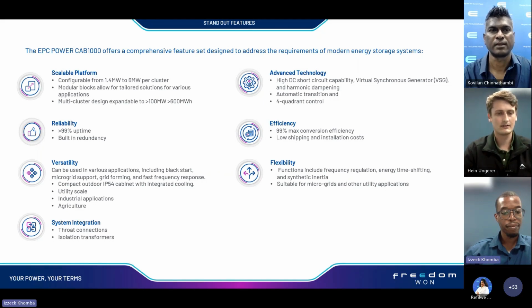It's quite a versatile solution that can be used in various applications, but some of the key features are black start capabilities, supporting a microgrid by being grid forming, and very fast adjustments in frequency. Another versatile selling point is the weatherproof cabinet with its own environmental management system to manage the environment on the inside of the inverter, with a cooling system and or heating as well for cold climates. It can be used in multiple sectors from utility to agriculture.